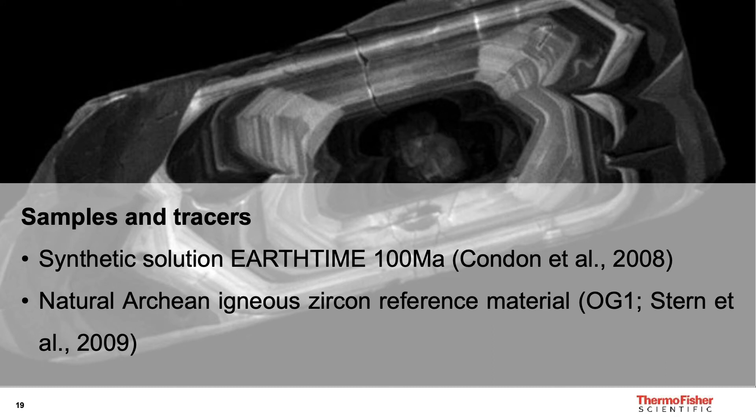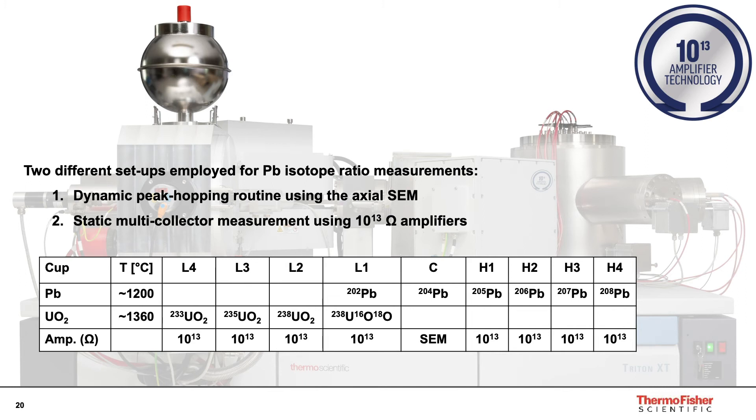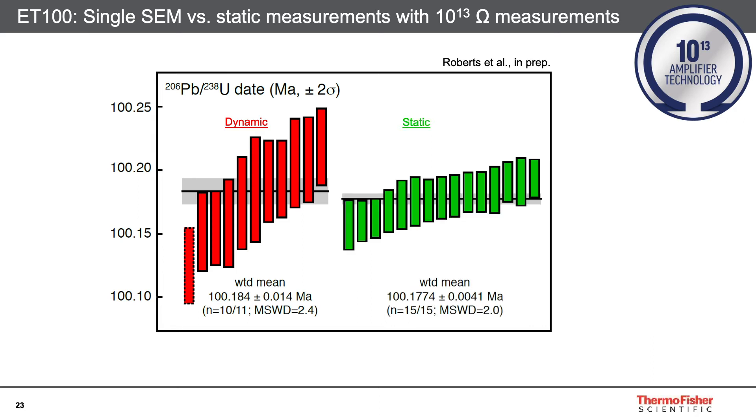To demonstrate this, we're going to show uranium-lead dates measured on two samples: first, a synthetic solution called EARTHTIME, and then a natural Archean igneous zircon reference material called OG1. These samples were analyzed at ETH on a Triton series TIMS equipped with eight 10^13 ohm amplifiers. Here are the 206-238 dates for the ET100 synthetic solution, with samples determined by dynamic peak hopping shown in red and those determined by static measurements on the 10^13 ohm amplifiers shown in green.